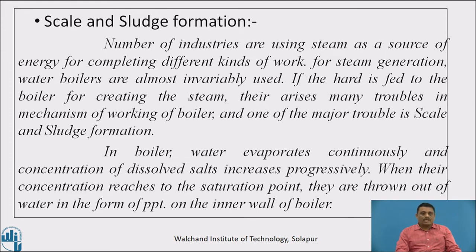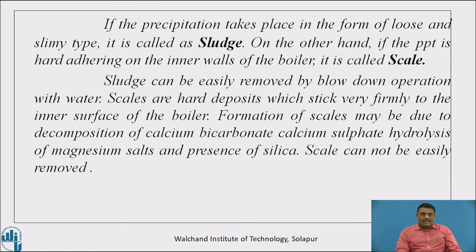In a boiler, water evaporates continuously and the concentration of dissolved salts increases progressively. When their concentration reaches saturation point, they are thrown out of the water as precipitate and get deposited on the inner walls of the boiler. If the precipitation takes place in a loose and slimy form, it is called sludge. If the precipitate is hard and adhering to the inner walls of the boiler, it is called scale.